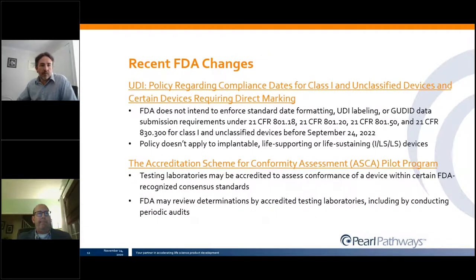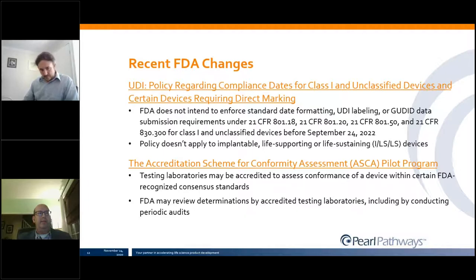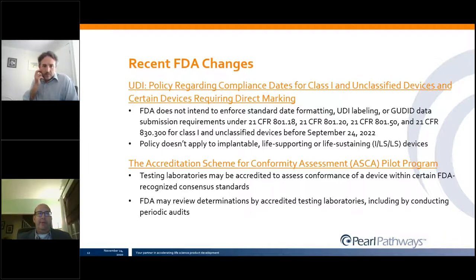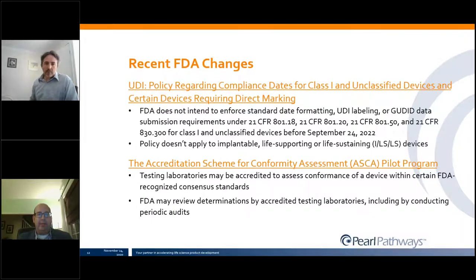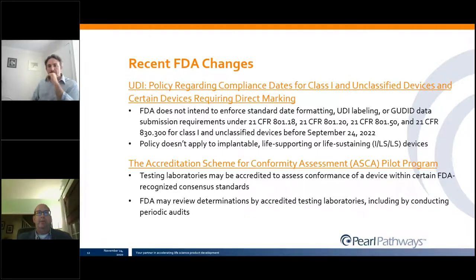Turning to FDA changes: FDA published a new guidance on UDI policy regarding compliance dates for Class I and unclassified devices. FDA makes clear that it does not intend to enforce standard dating or UDI labeling for Class I or unclassified products before September 24, 2022. This does not apply to implantable or life-supporting or life-sustaining devices, even if they are considered unclassified.